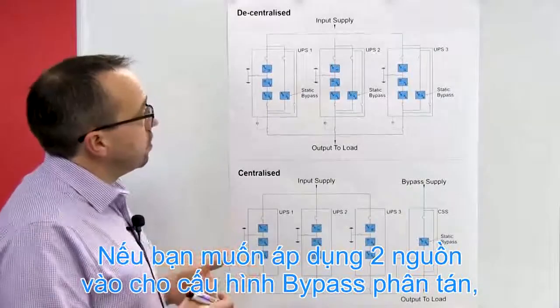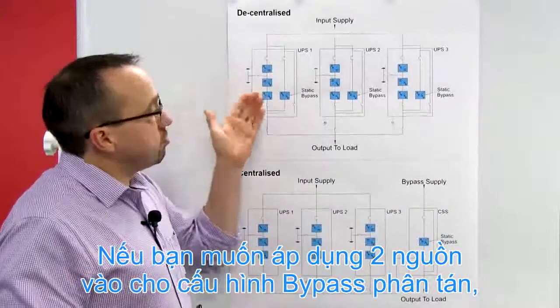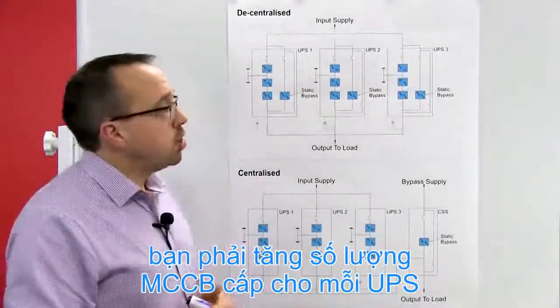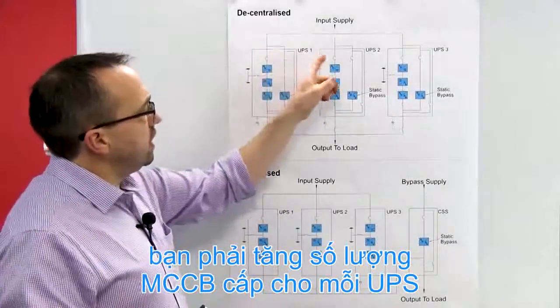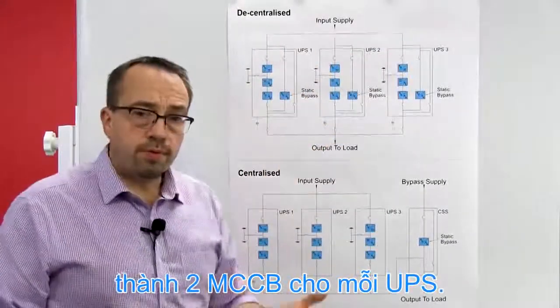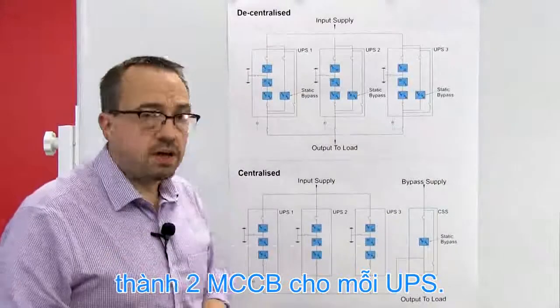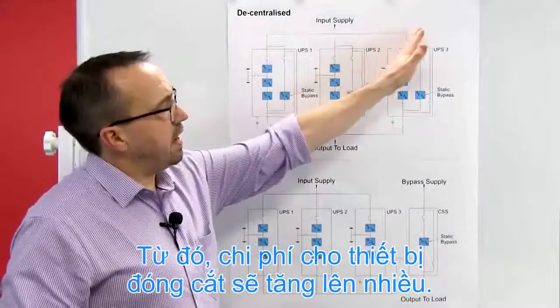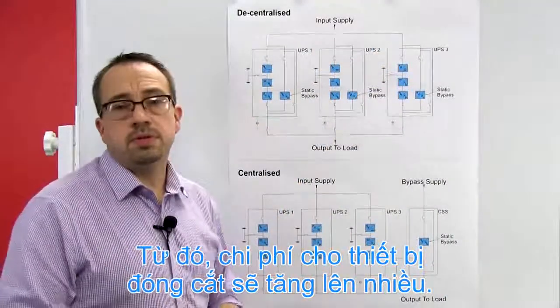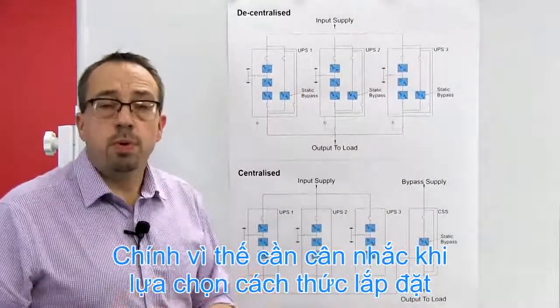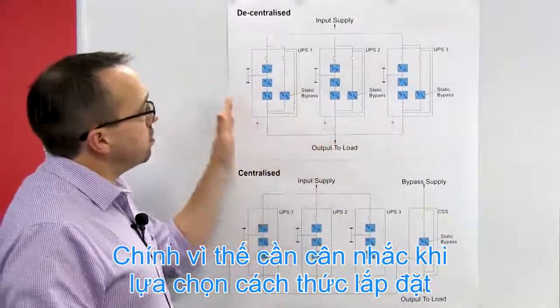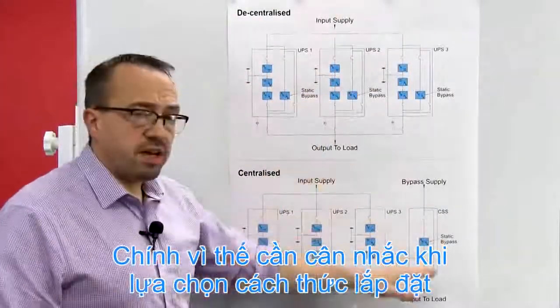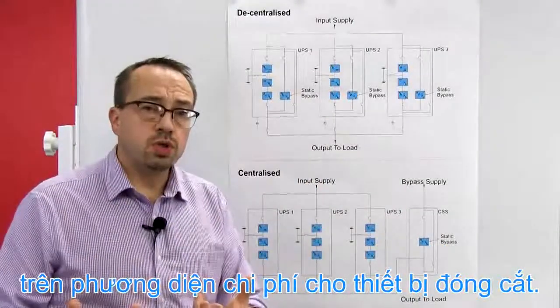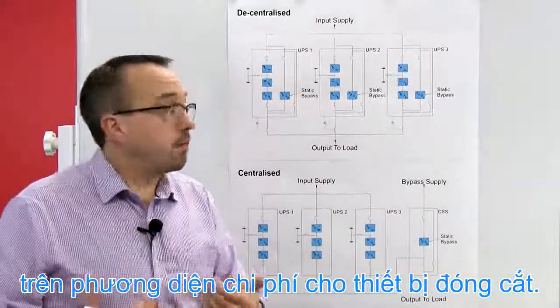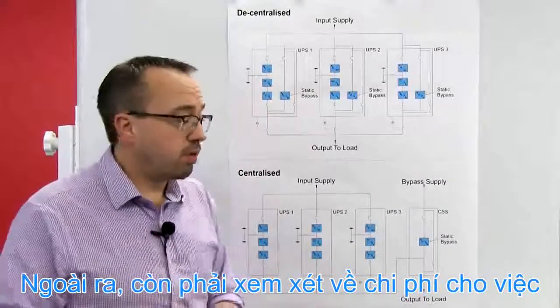Now if you wanted to apply that to the decentralized solution up on the top diagram, you would have to increase the number of breakers feeding each UPS to 2, one for the rectifier and one for the bypass line, and therefore the switchgear would have to contain 6 input circuit breakers. That's 2 per UPS system, and therefore you must consider the installation method in terms of the additional costs of the actual switchgear, which is typically overlooked.